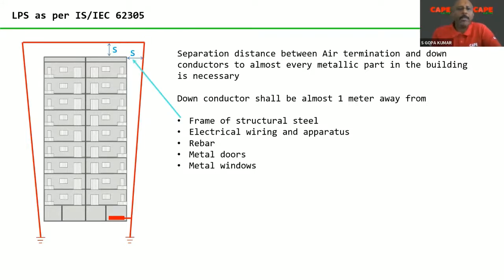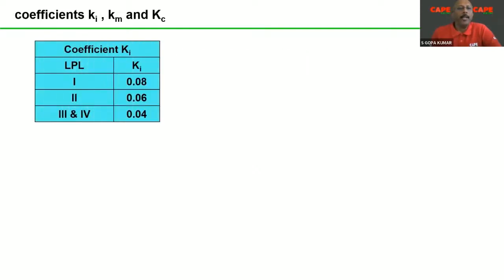Now, how is the separation distance calculated? There are constants. For example, depending upon the level of lightning protection, 1, 2, 3, 4, the constants are given in the standard. Depending upon the insulating material, air or concrete, wood or brick, the values are given. You always select the most unfavorable material. For example, in the next slides you will see how this has to be done. Then the coefficient, like the number of down conductors, one down conductor, two, three, and more, these constants are always given in the standard with some notes. Please have a serious look at that.